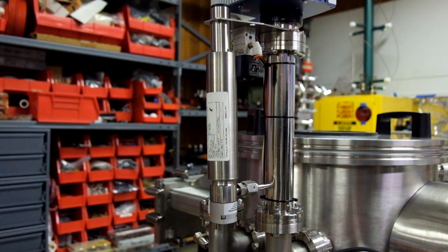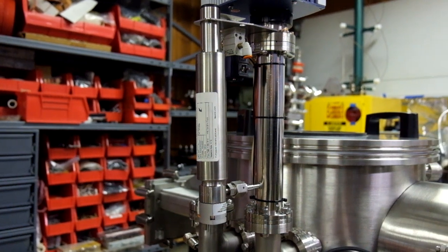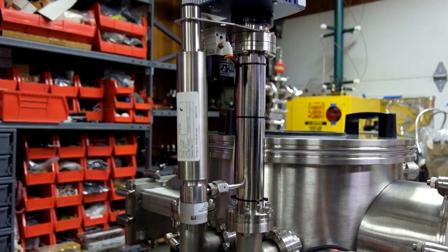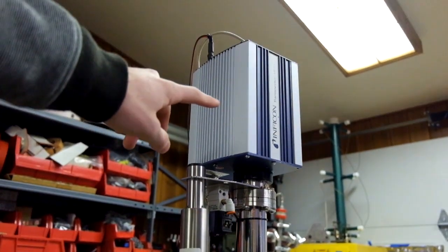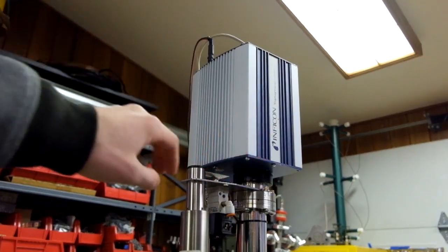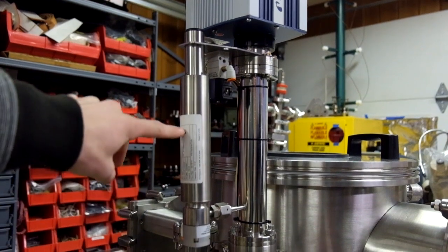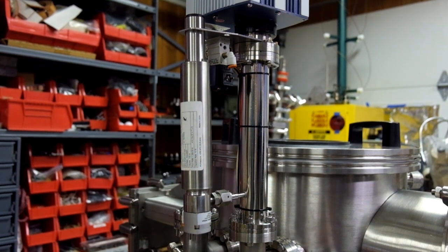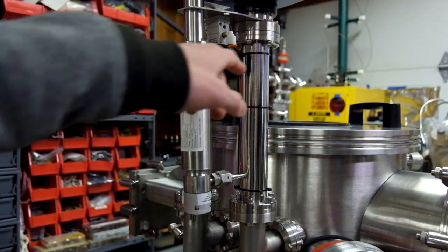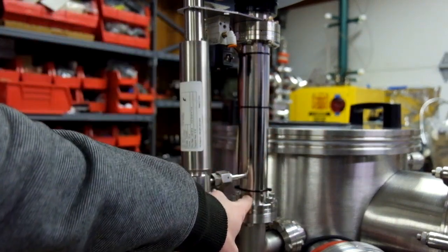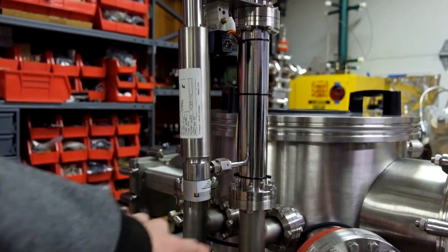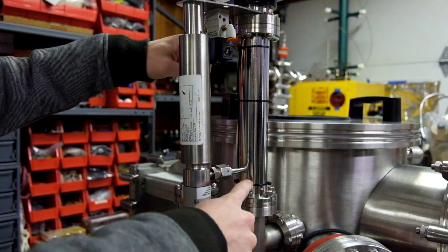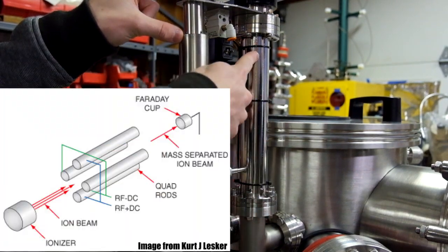You can have a thermocouple gauge and a capacitive gauge and sort of start guessing at what's going on in the chamber beyond just the pressure, but it really is just guessing. So here's the RGA. On top in this bluish-white box are the RF generator and the rest of the electronics. This is a 99.999% argon source so you can flow that into the chamber very slowly to calibrate the device — I don't have that hooked up right now, but it's pretty well in spec. The actual analyzer connects through a 2¾-inch ConFlat to the rest of the chamber.